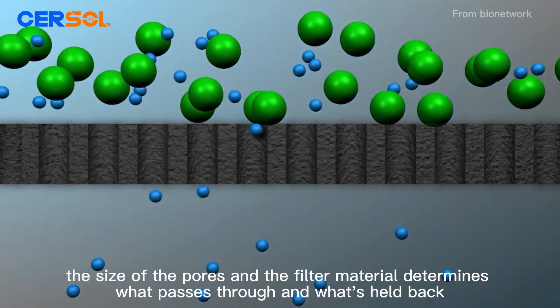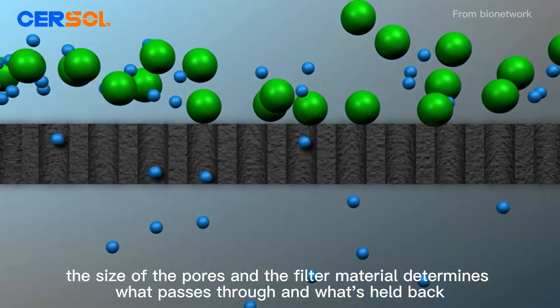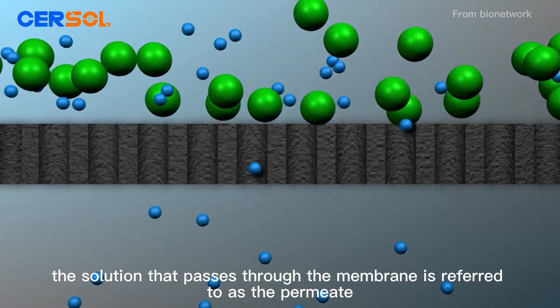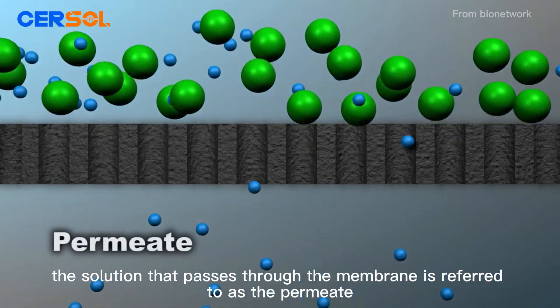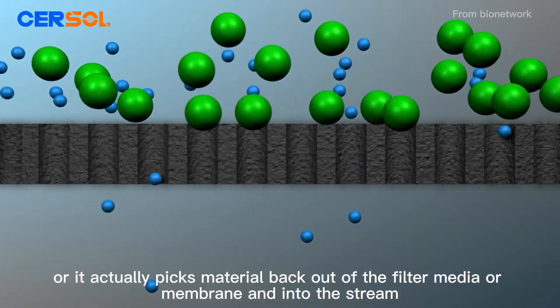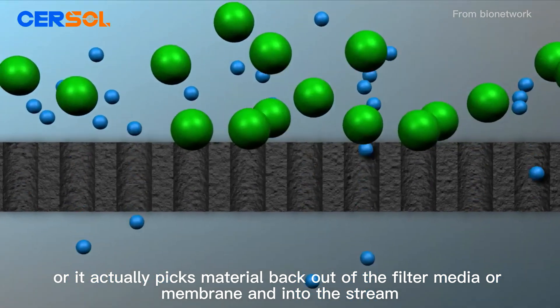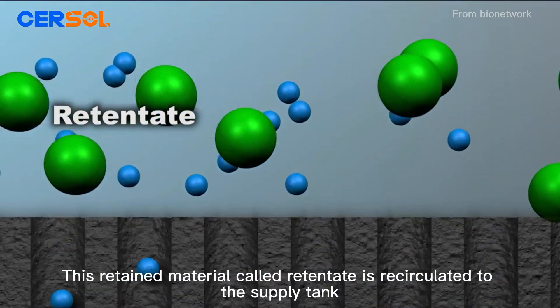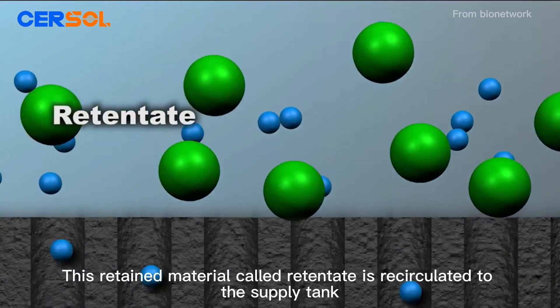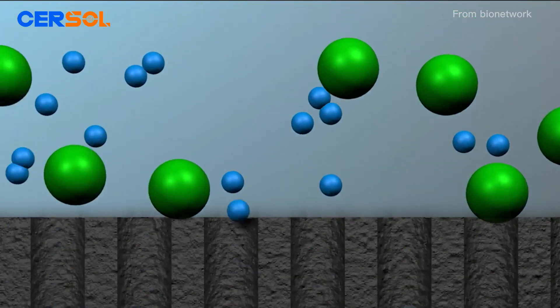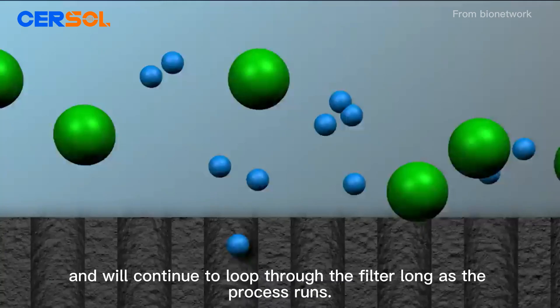The size of the pores and the filter material determines what passes through and what's held back. The solution that passes through the membrane is referred to as the permeate. This retained material, called retentate, is recirculated to the supply tank and will continue to loop through the filter as long as the process runs.